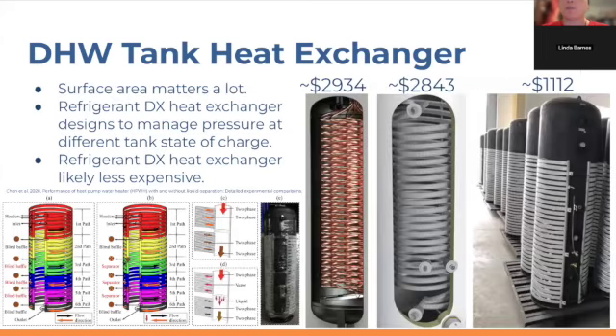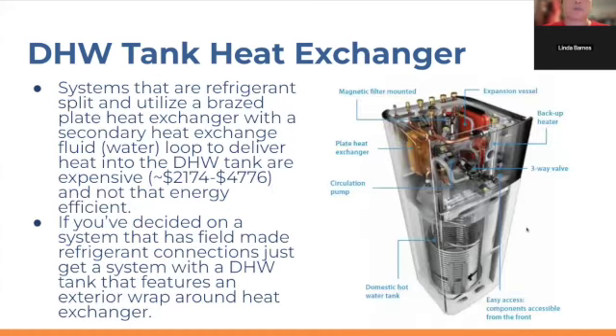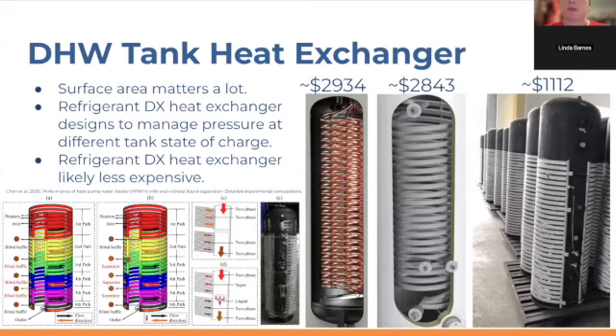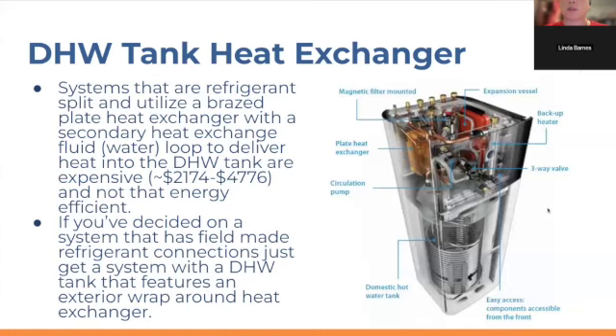So this design is quite expensive, and you can imagine that it's not nearly as efficient as delivering the heat from the refrigerant straight into the water through the tank wall, without needing that secondary heat exchange fluid. And so, if you choose to go with a refrigerant split system, it would be best to pick a manufacturer that can sell you a system with a wraparound, refrigerant-to-tank heat exchanger, rather than one with this design. This is an older design that may disappear in the next few years.